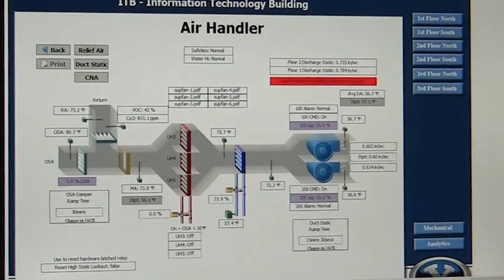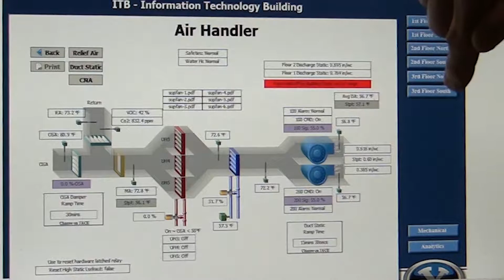All right, so something doesn't look right. Casey pointed out we've got 72 before our chilled water coil, and 72 right after it, but then the fans have this amazing cooling effect now—these new high-tech fans cooled it all the way down to 56 degrees. Chilled water fans? So something's not right there.